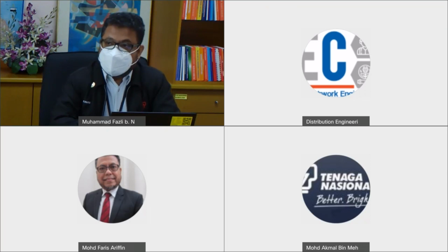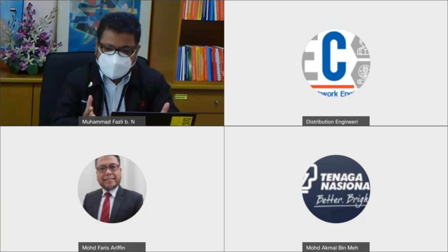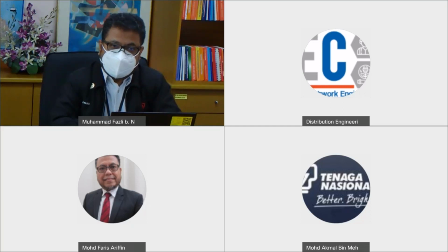And again, it is a requirement. If you find that you have a very high pole footing resistance or tower footing resistance, it can be improved with the use of earth enhancement compound, which is actually made of bentonite, to improve the performance of the earthing. But we need to use counterpoise earth tape, copper tape, and also copper rod to ensure that the dissipation of lightning surge or lightning current to ground is effective. I hope that answered the question.